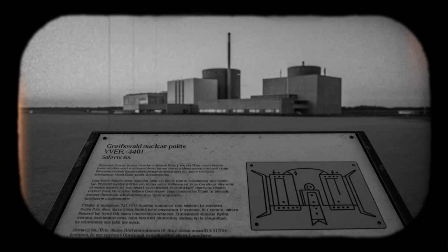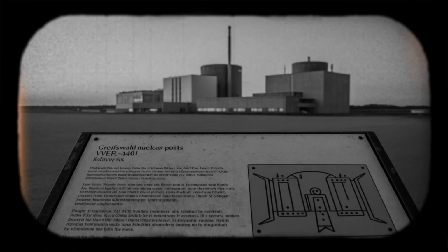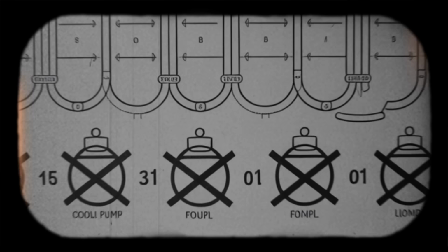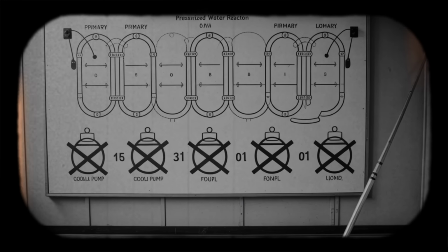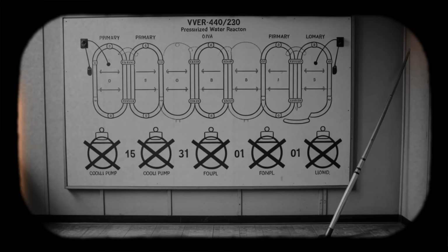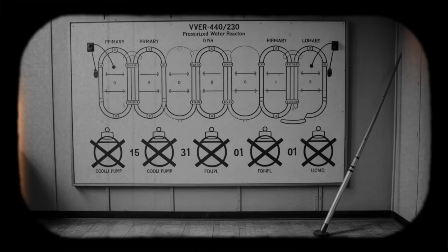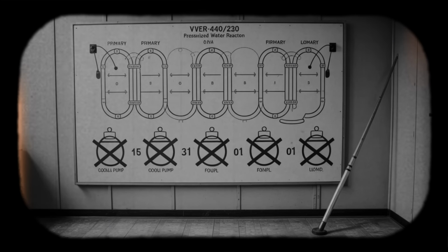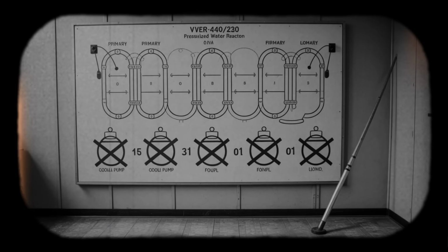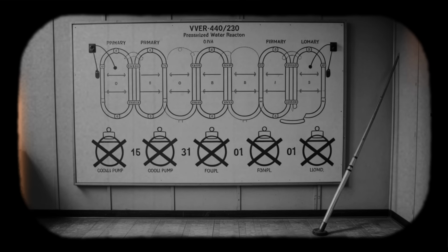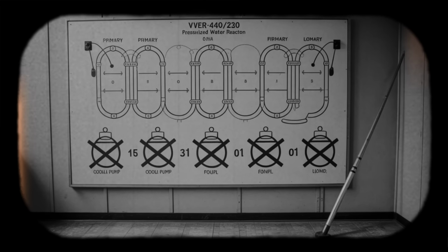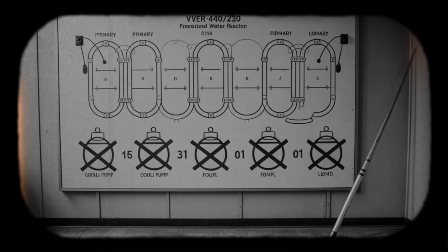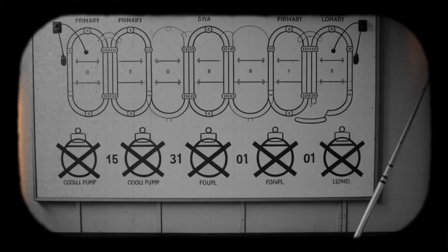On 9 October 1982, a similar fire-induced station blackout occurred at Armenia Unit 1, another VVER 440 V230. That event, combined with Greifswald's eventual disclosure, prompted systematic reviews of the entire first-generation VVER 440-230 fleet. IAEA safety assessments identified generic weaknesses: limited containment capability, confinement leakage potential, emergency core cooling system design constraints, and vulnerability to internal hazards including fires. Cable routing emerged as a recurring issue. First-generation VVER 440s often lacked robust separation between redundant safety trains, allowing common cause failures from fire, flooding, or other internal events.